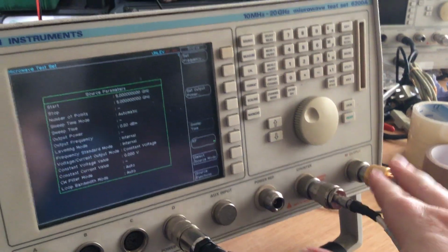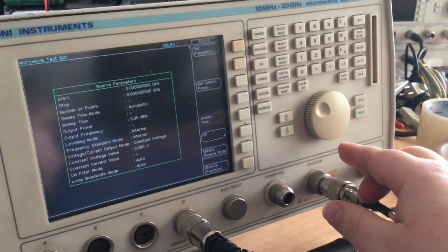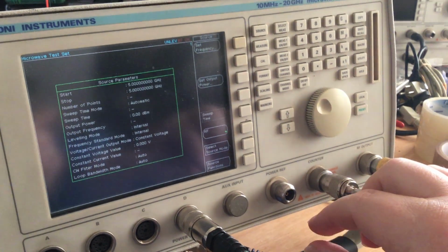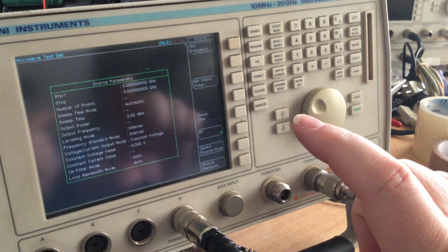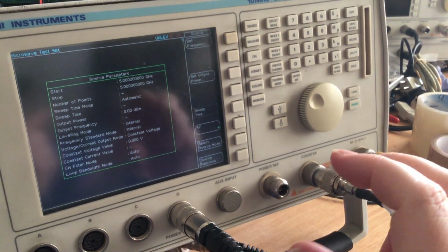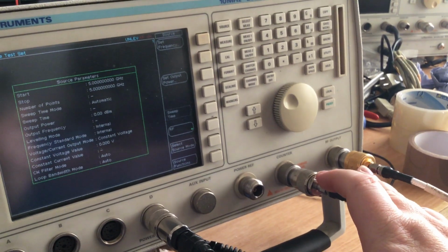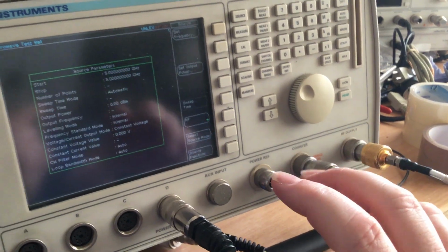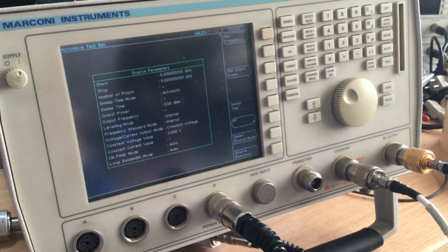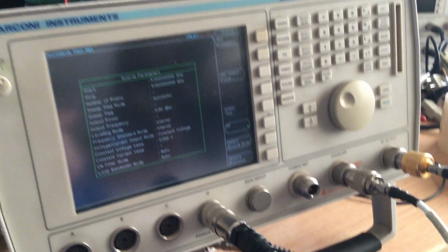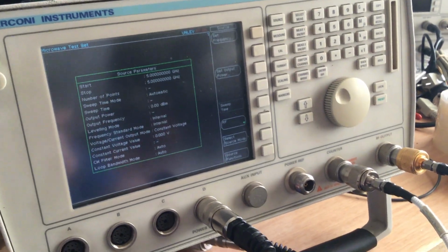The only time when the output changed is when you turn the level down enough so that the step attenuator, which I've shown you in the previous videos, that relay attenuator will click in and then the output level will drop 10, 20, 30, whatever dBs. So what we've done, we've reassembled the test set now back to how it was.